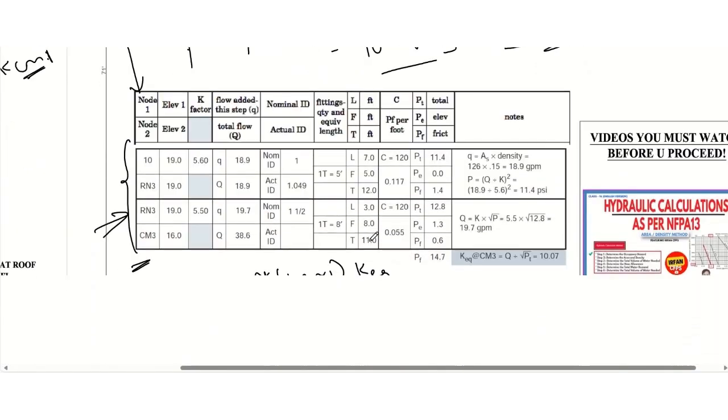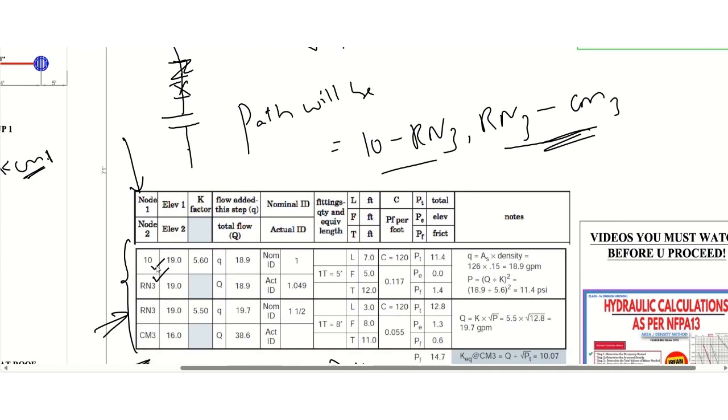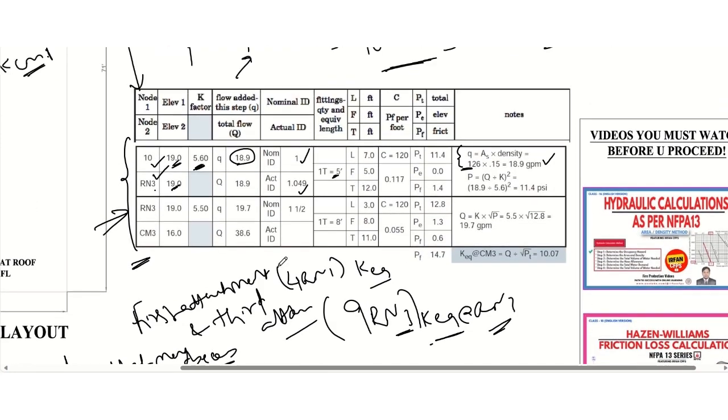Now we will move ahead with this particular case. Here you can see we have 10 to RN3. So the path will be 10 to RN3. 10 is at 19 feet elevation. RN3 is also at the same height. So the K factor here is 5.6 for the sprinkler, and the flow will be 18.9 GPM, which we calculated from this particular formula. And then we have nominal ID 1 and actual ID 1.049. And here we have one T as you can see, so you need to consider this T once again. We have T, so the equivalent length is five feet since the pipe size is one inch.